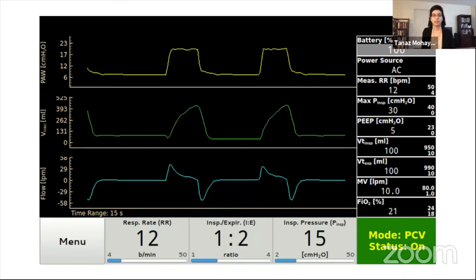In PCV mode, medical experts can set the respiratory rate, the maximum pressure, and the inspiratory to expiratory ratio. Those are all the parameters at the bottom of the display. The numbers on the right side are the measured values that get reported. There are also some smaller numbers in the same right-hand column, which are the minimum and maximum values below and above which the alarm will go off.